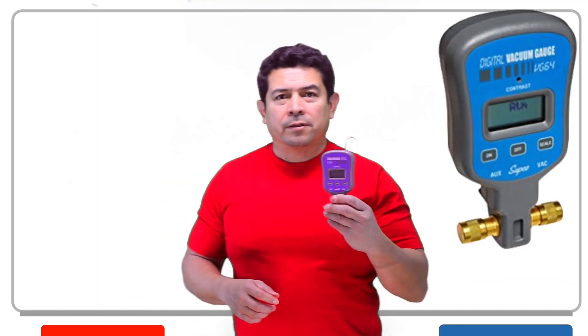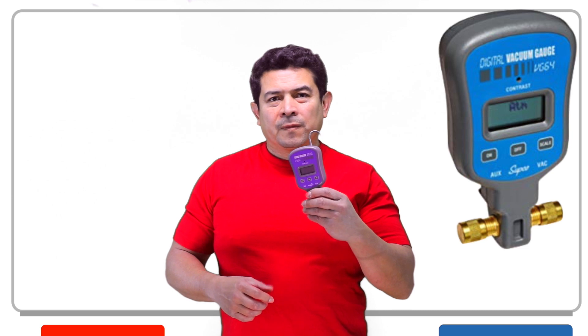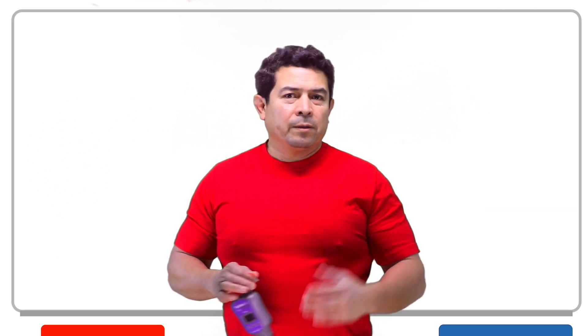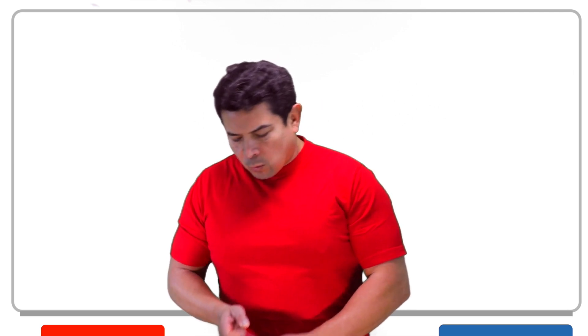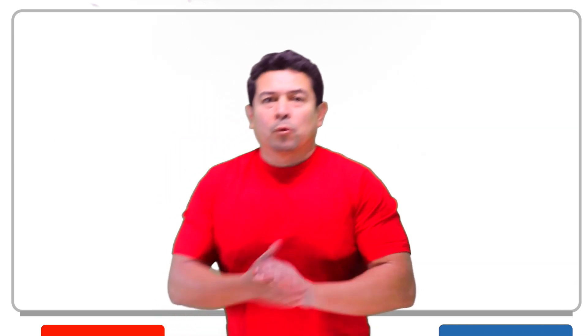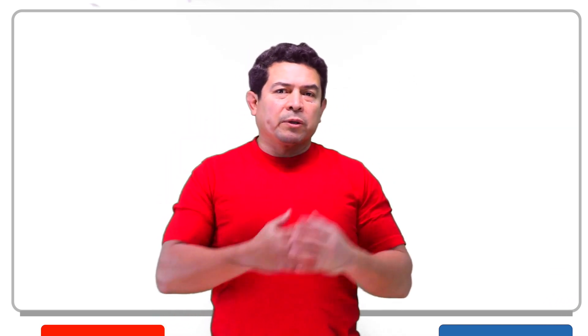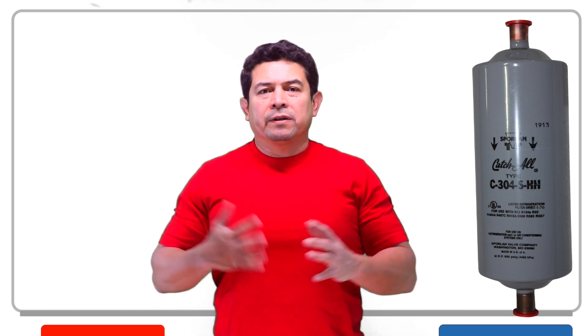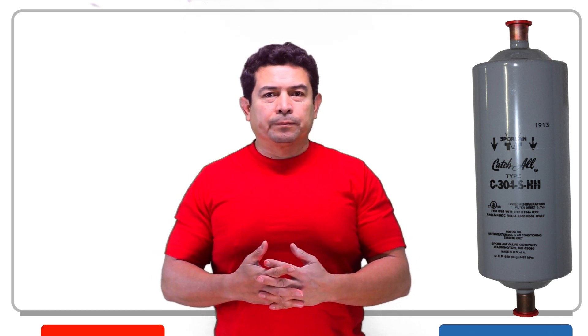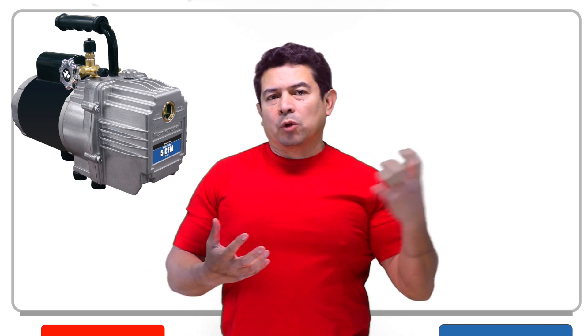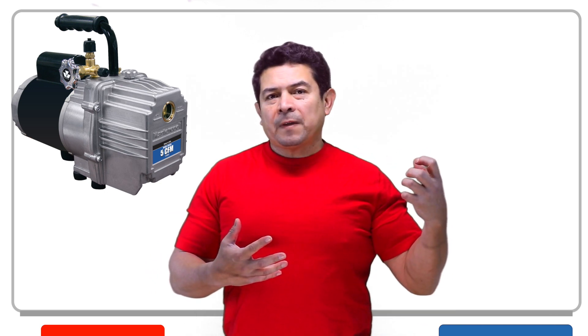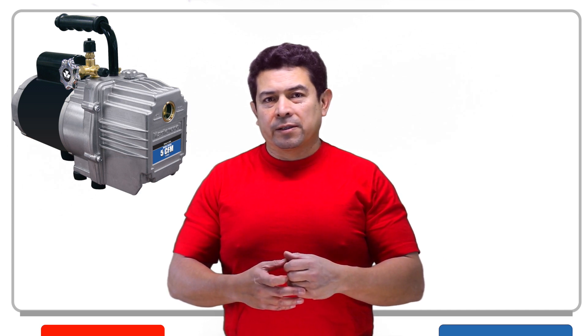I wanted to talk about your micron gauge. We know that we're supposed to pull a vacuum down to 500 microns when we have opened up a system. We're also supposed to replace the dryers, put a new dryer in every time you open up a system, and we need to pull a vacuum so that we can recover all of the air and non-condensables that's in the system.